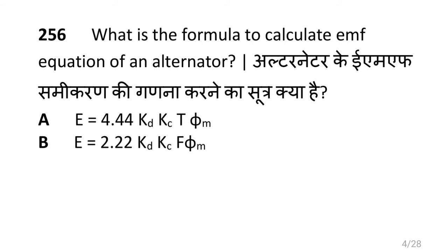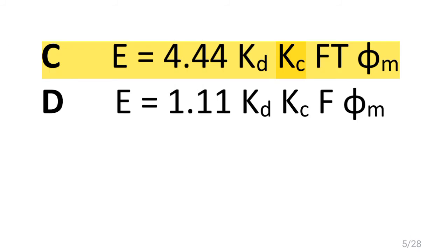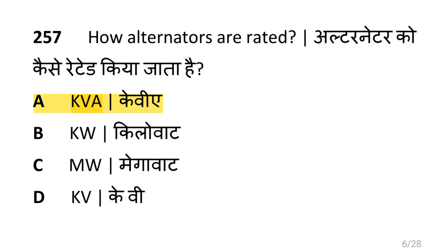What is the formula to calculate EMF of an alternator, i.e. E is equal to 4.44 × Kd × Kc × F × T × Φm, where Φm is the maximum flux? How alternators are rated, i.e. KVA?